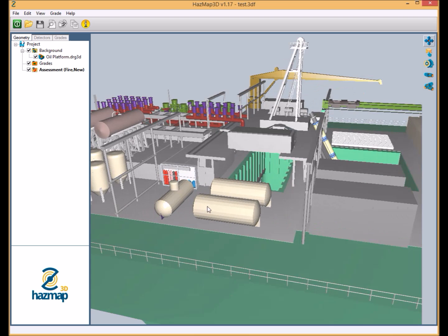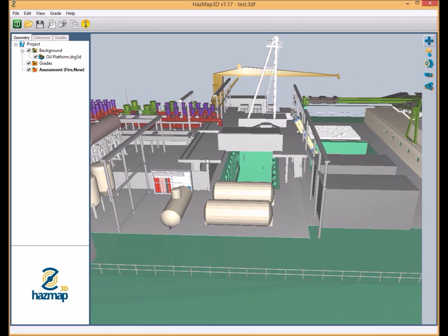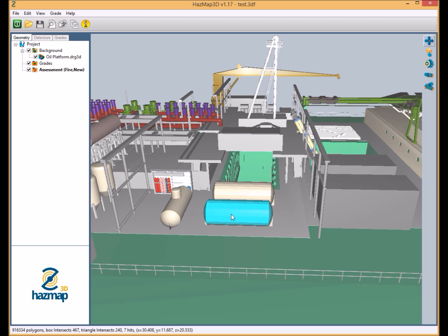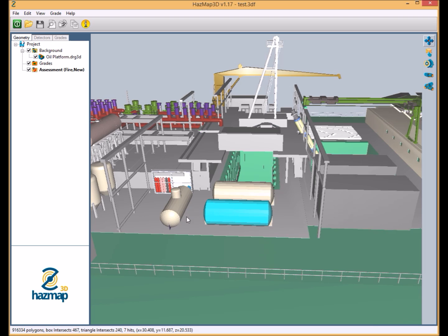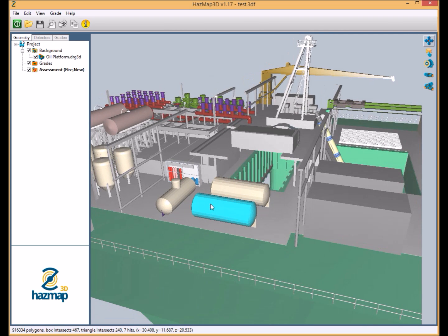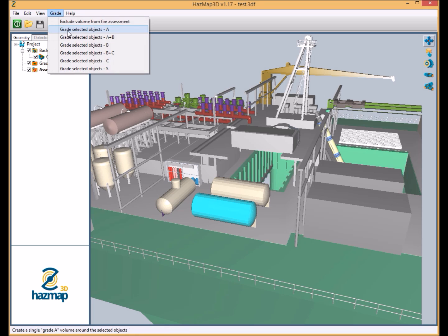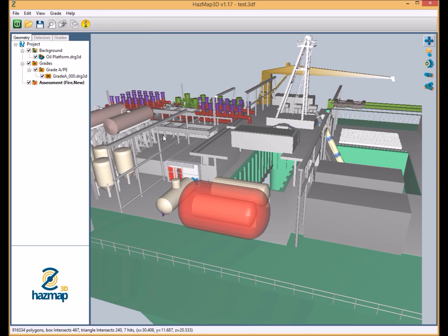So I'm just going to add some grades into this small process area here. I'm simply going to double click on the vessel and we'll grade this grade A. Obviously, what grade A actually means can be completely user configured. The distance that extends from the vessel and also the kind of target fire sizes we typically expect to see, whether it's a 1 out of n or 2 out of n voted system.